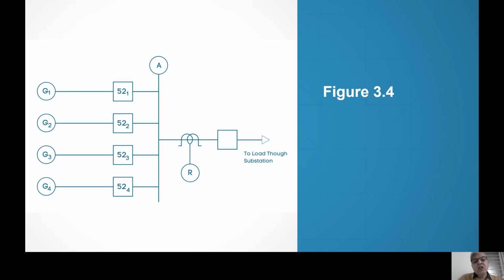Not only that, but because the fault current has also changed, with only two generators running, and your time multiplier setting is dependent on fault current, therefore the time multiplier setting will also change at night time. It is also quite possible that the ZS by ZL ratio, where ZS means generator to relay, changes. Four generators means ZS is small, so ZS by ZL is small. But at night time, ZS by ZL is large. So it is quite possible that at night time you may need relay R to be a very inverse relay, while at daytime it should be a normal inverse relay.